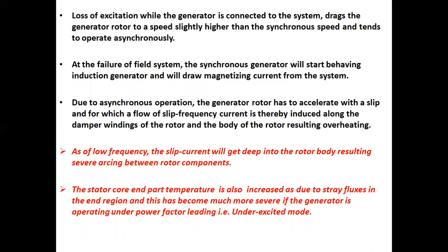Most importantly, as of low frequency, the slip current will get deep into the rotor body, resulting in severe arcing between rotor components. The stator core end part temperature is also increased due to stray fluxes in the end region, and this becomes much more severe if the generator is operating under power factor leading, that is under excited mode.